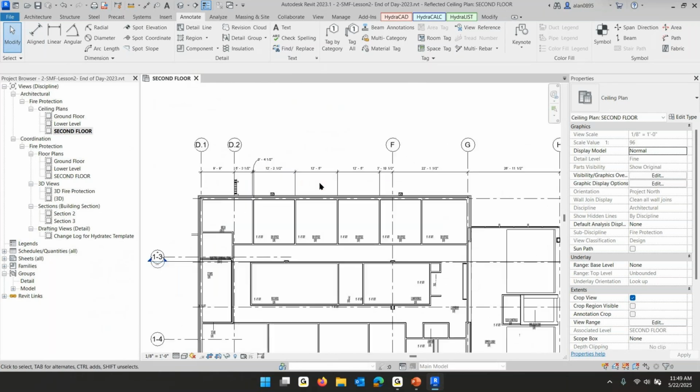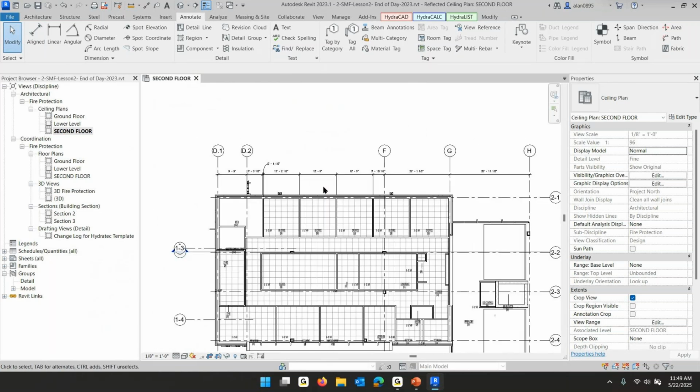One thing I guess I've got to warn you about: in AutoCAD, you can dimension from this point in space to that point in space to that point in space. In Revit, it says no. Dimensions are to things. So you can't just pick willy-nilly any old place in the world. When you use a line, the first thing you pick has got a line, and your dimension is now perpendicular to that. And every other object you pick has got to have a line in it that's parallel to that first object that you picked.